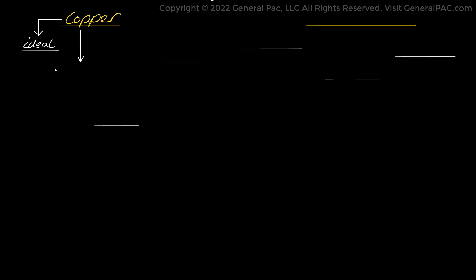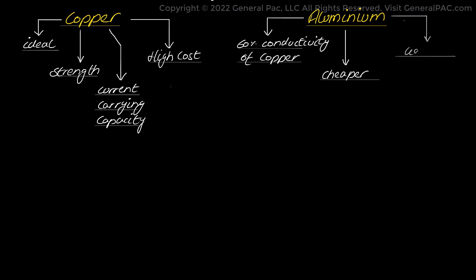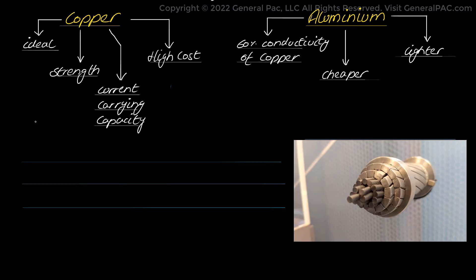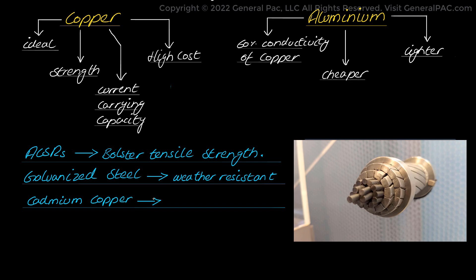Copper is no doubt the ideal conductor for transmission of electrical power owing to its great mechanical strength and more current carrying capacity than any other material. However, its cost is high and reserves are few. Aluminum has 60% the conductivity of copper and is relatively cheaper and lighter, giving it an edge over copper and therefore it is more commonly used. Aluminum alloys reinforced with steel, or ACSR, are also used to bolster tensile strength and give better conducting properties. Galvanized steels have very high tensile strength and are used in areas where weather conditions are very abrupt, and cadmium copper is used for extremely long distances.